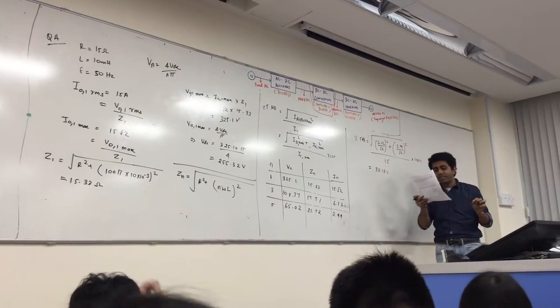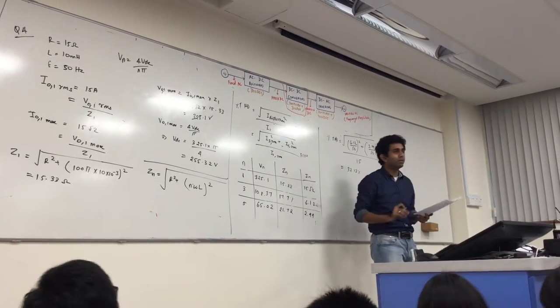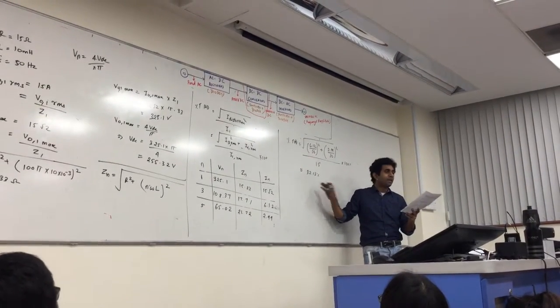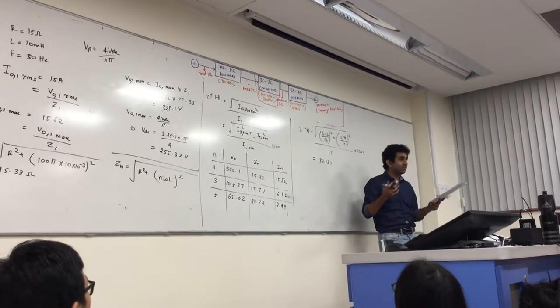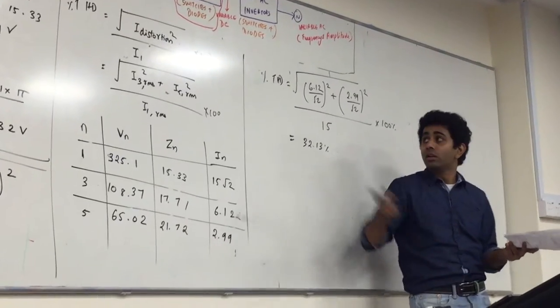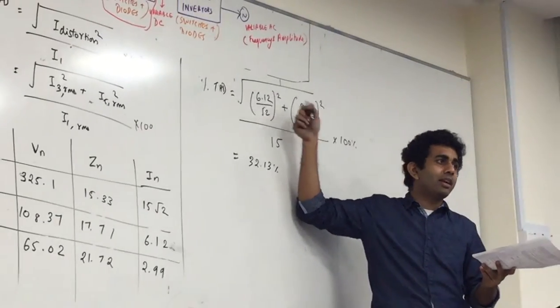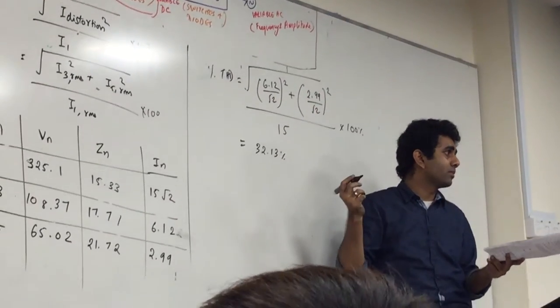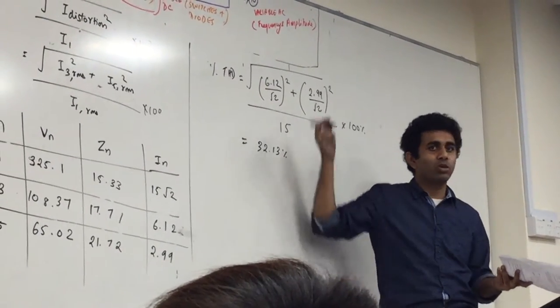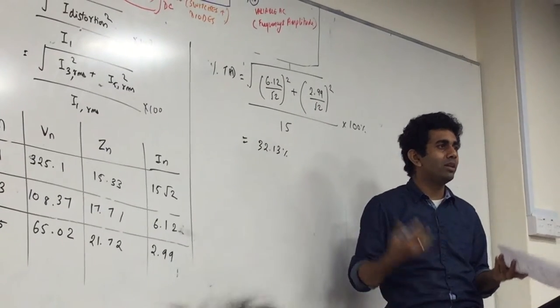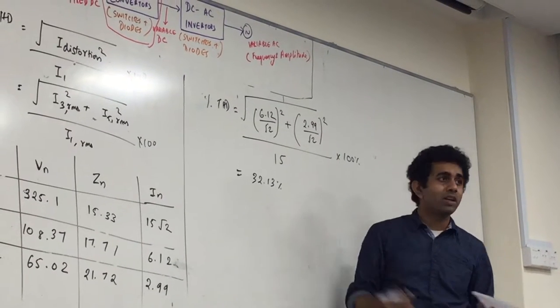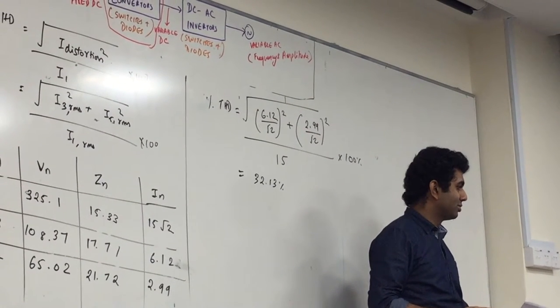It is intended to reduce the THD of the load current to below 15%. Currently it is 32%. Suggest a suitable scheme to achieve it. Which reduction would make it less than 15%? I3 or I5? I can try both, but you'll realize that only if I reduce I3 is going to be less than 15%. Actually it's 14% I think.